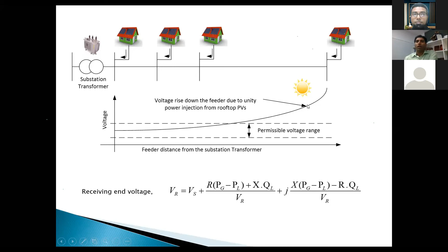What we devised was a droop-based battery controller working in conjunction with the PV inverter. This was a highly cited paper we wrote a few years back. The idea was to arrest the increase in voltage before it gets bad. As voltage starts increasing, you see the droop and start charging the battery. Once it reaches a certain level, designed by the algorithm, you use reactive power if available, limiting the size of the battery needed, since storing everything in the battery would be too costly for customers.